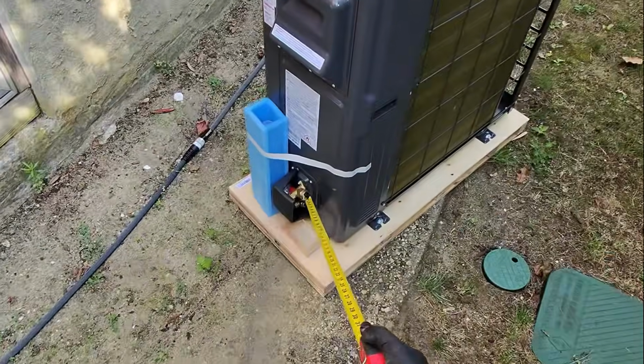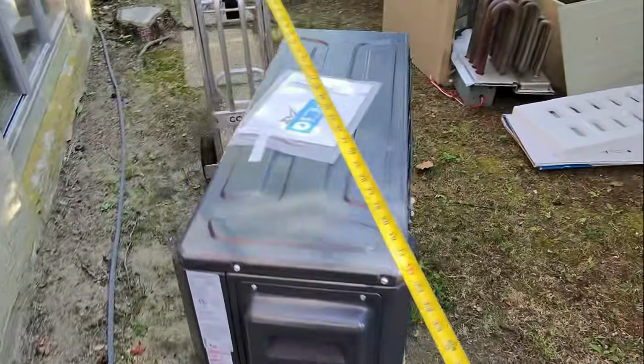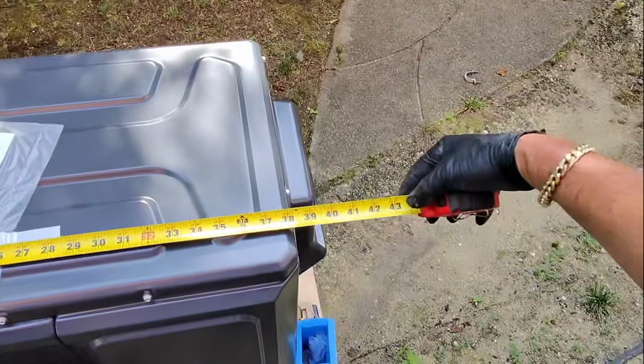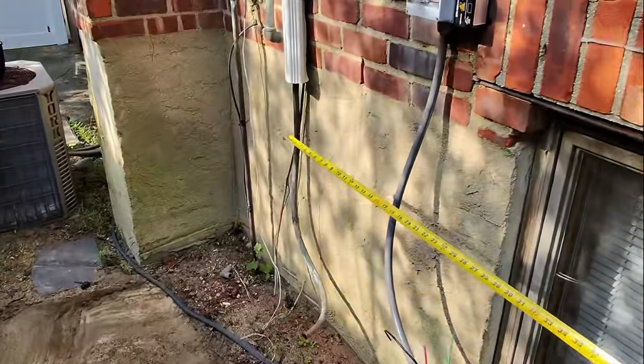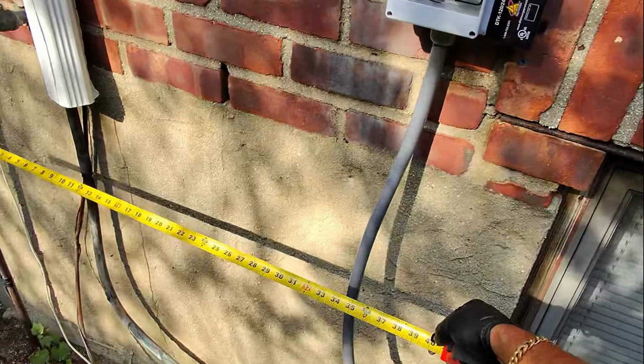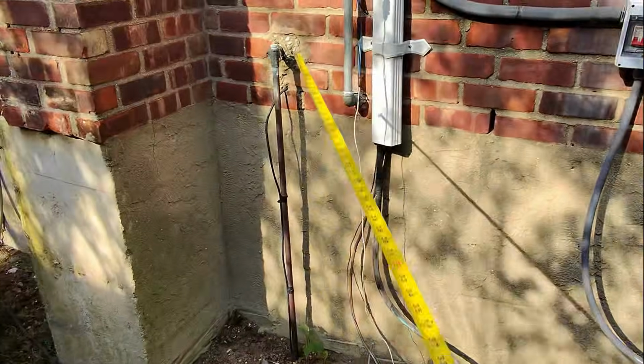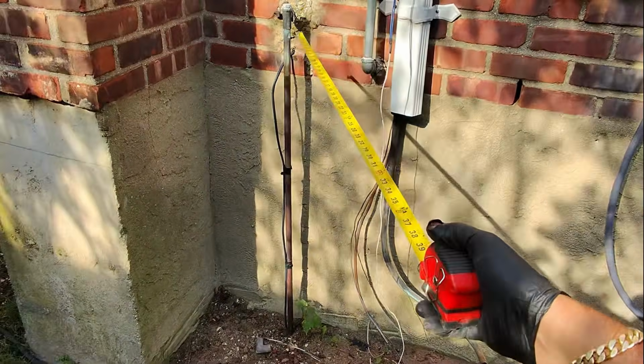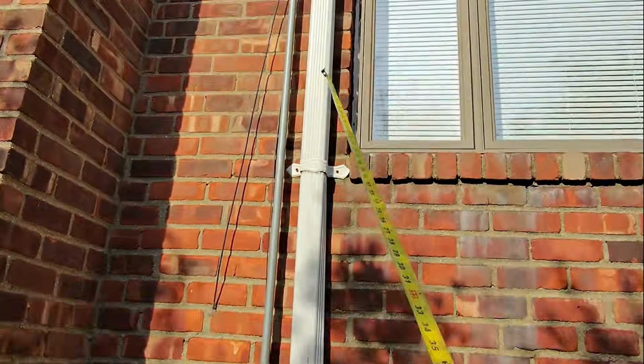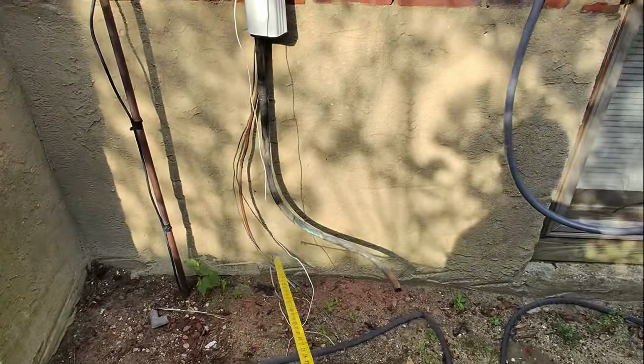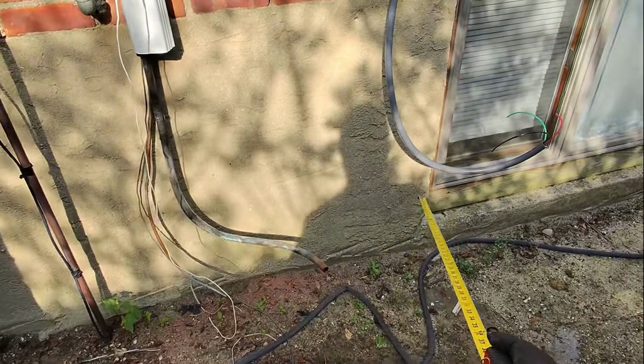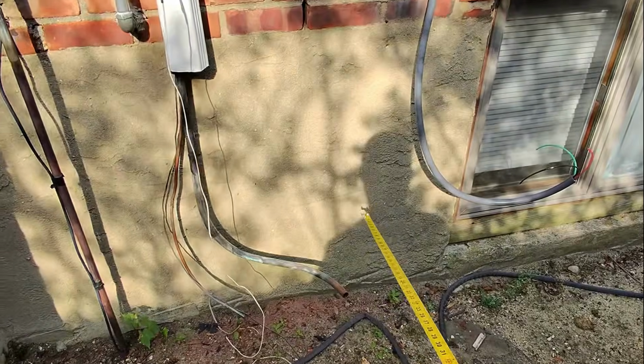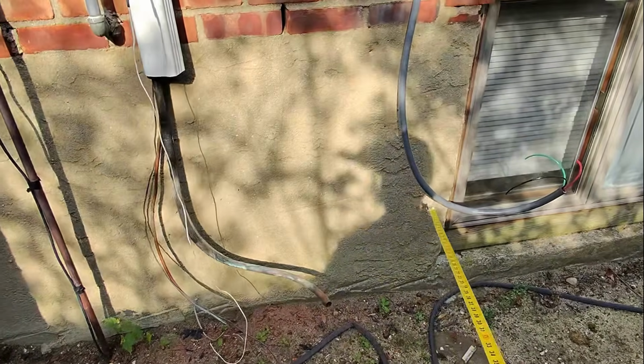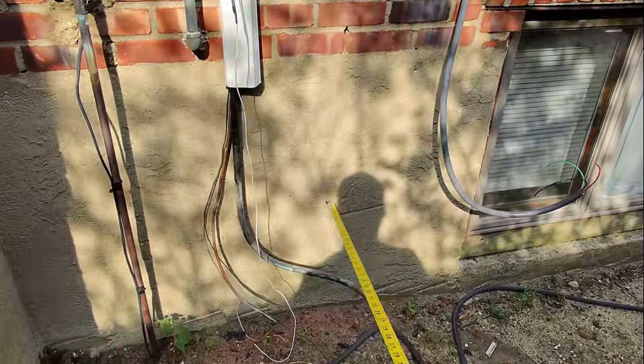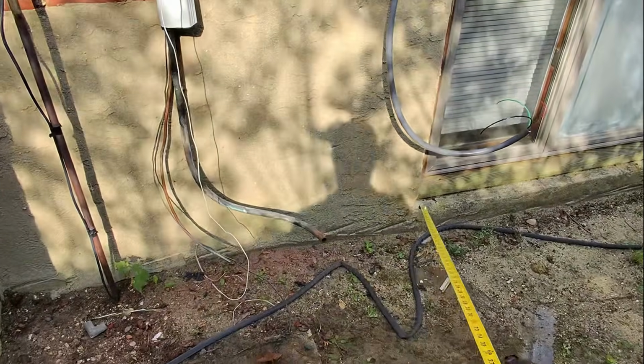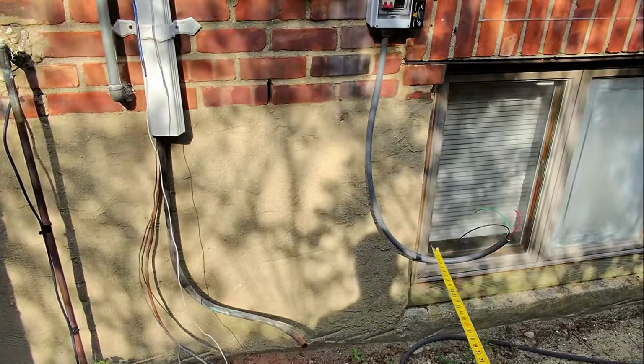See? Installs just like a ductless mini split. Now the overall width of this unit, roughly around 40 inches. 40 inches puts us right here. Okay? We'll clear the window. We'll clear this irrigation line, 3/4 inch irrigation line, and this gas pipe is abandoned, so I'm not worried about that. We're going to keep the unit off the wall about 6 inches. The manual calls for a minimum of 4 inches from the back of the unit to the rear surface, and we're going to try to keep it about 1.5 feet off of grade. Now that 40 inches is perfect now.